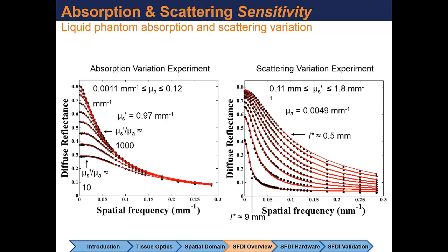So if you think about DC for a second, planar illumination on its own, you send light in. If you send 100% of the light in, you'll get, in this case, 78% of the light back. If you look at the modulated component on top of the DC, at whatever frequency that's not DC, there's less and less. So when I represent diffuse reflectance, this is on an absolute scale for each frequency component. There's a lot of calibration that goes into making sure this is an absolute measurement.